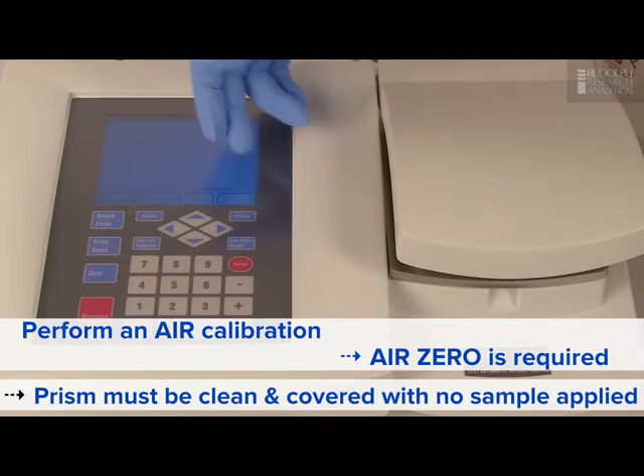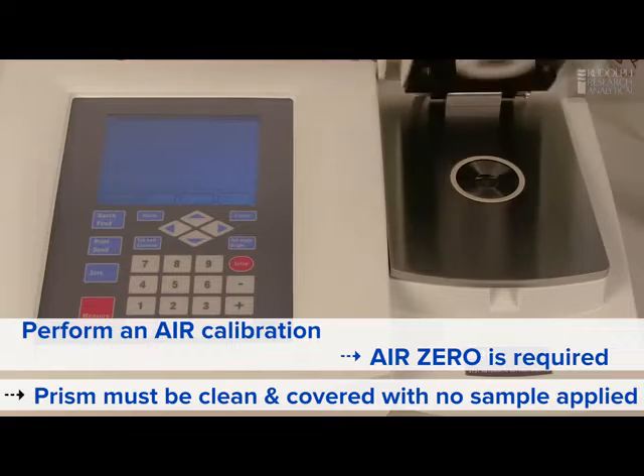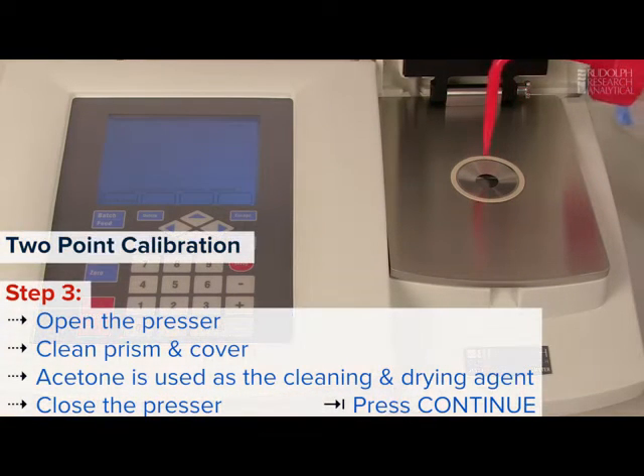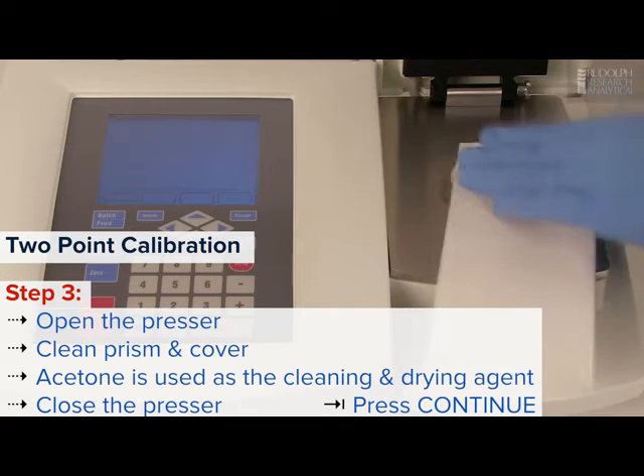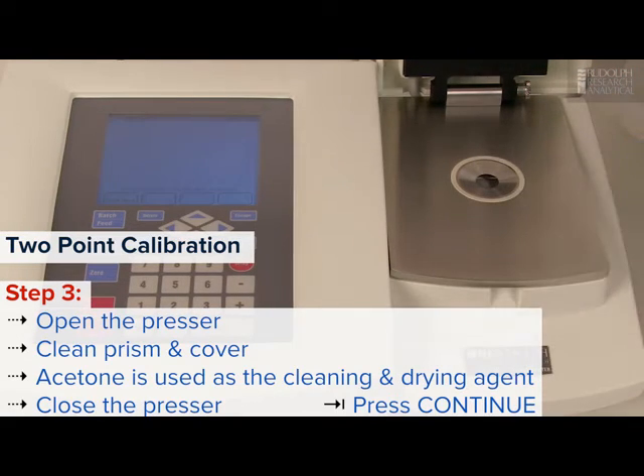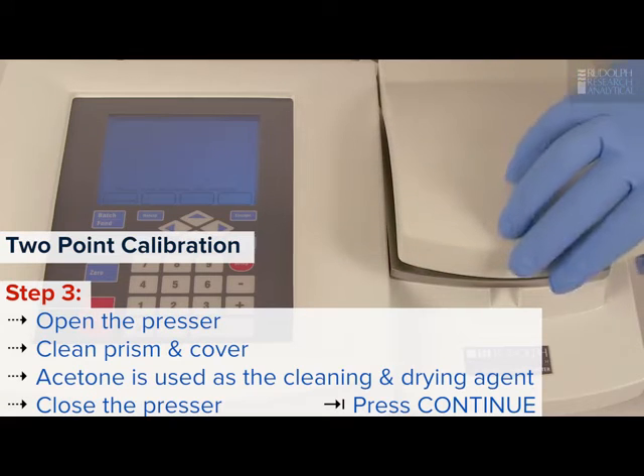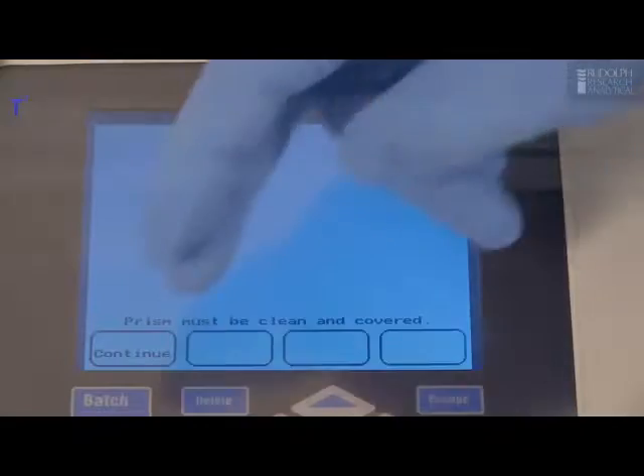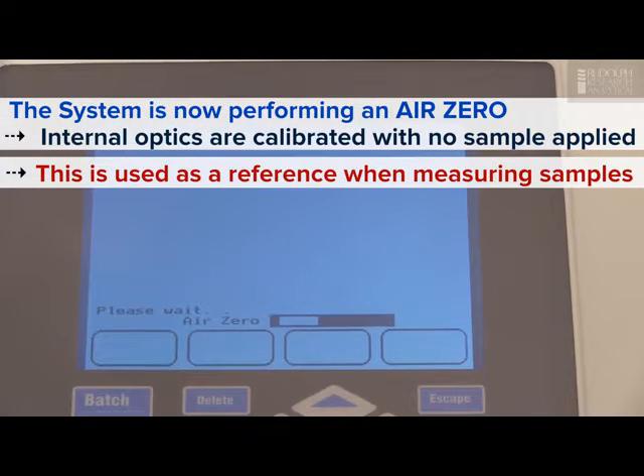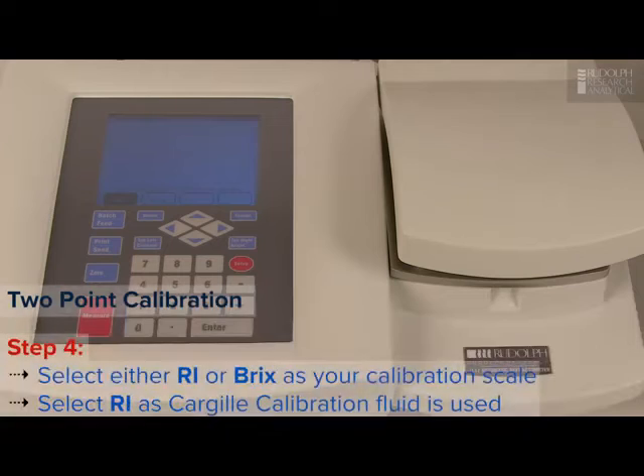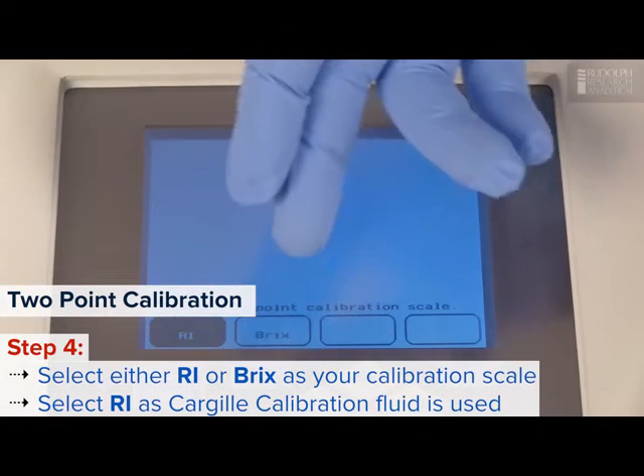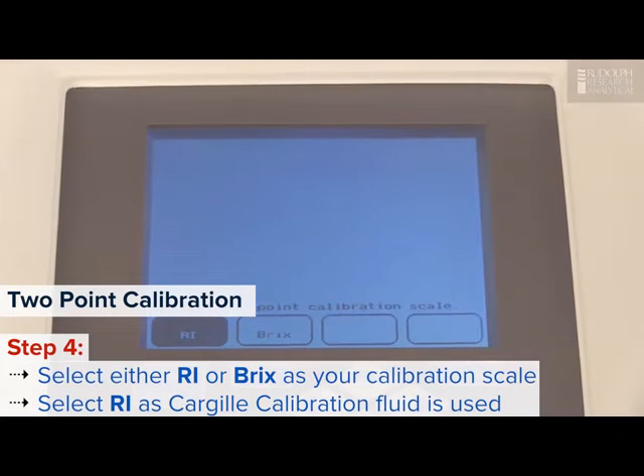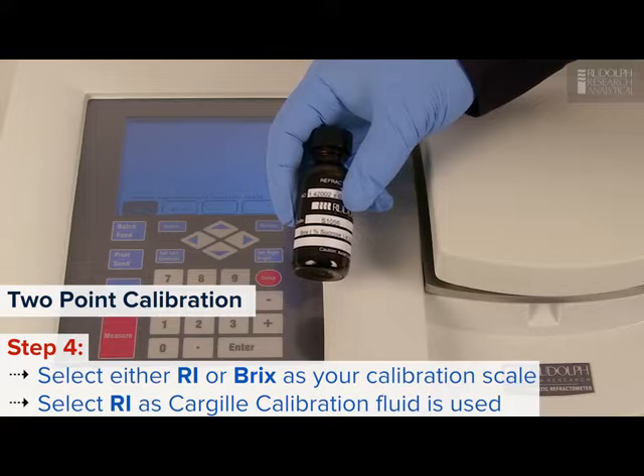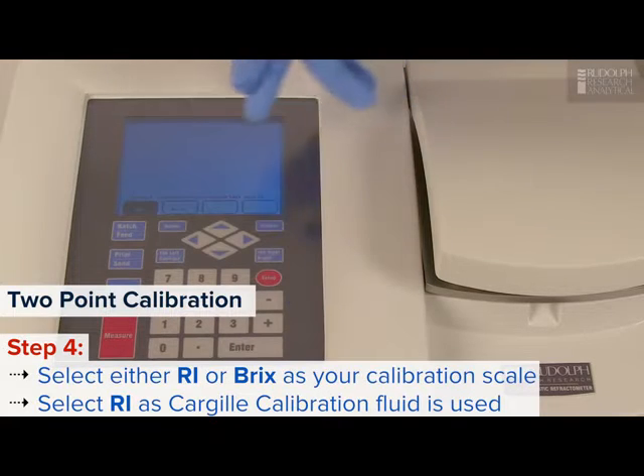The prism must be clean and covered with no sample applied. So we're going to use acetone to clean the prism. Acetone dries up instantly. And close the presser. Press continue. So what the system's doing now is it's calibrating the internal optics with no sample applied, which it uses for reference when you do place a sample on the prism. Once the air zero is complete, it's going to ask you to select between refractive index and Brix. In this case, we're going to be using the refractive index scale. So select refractive index.